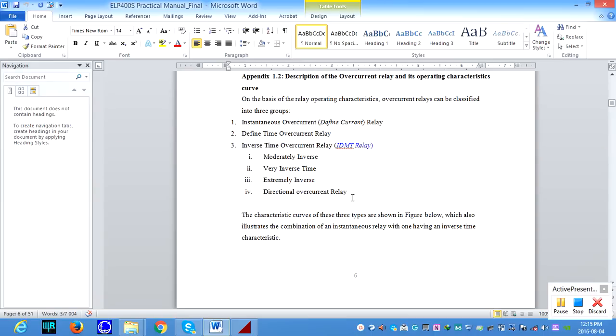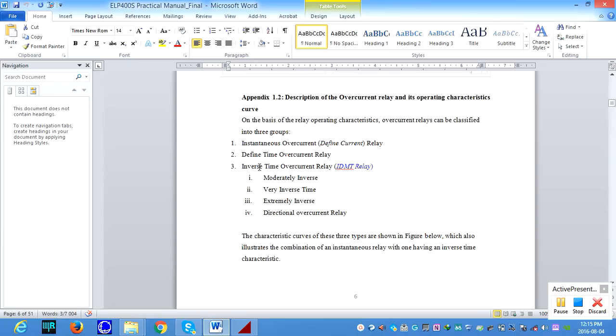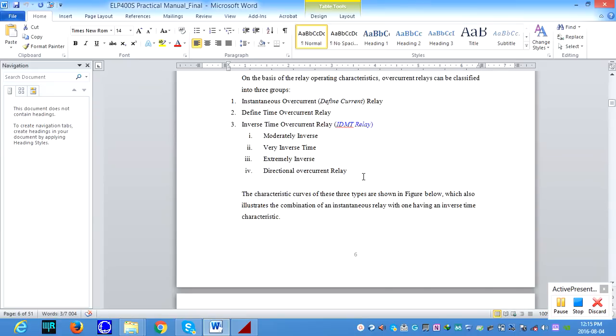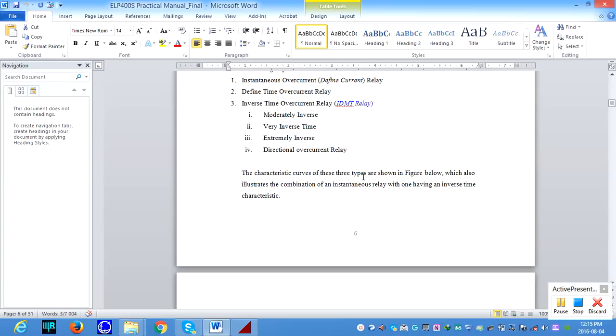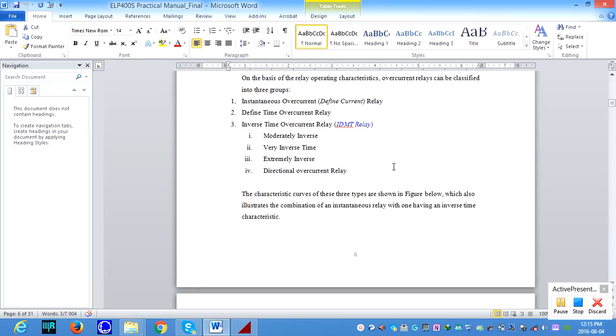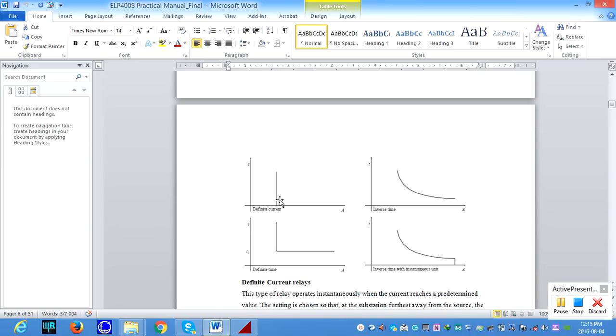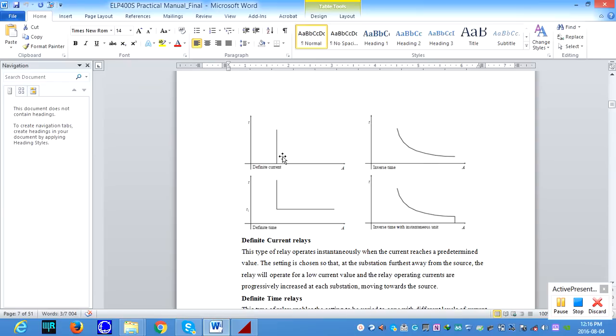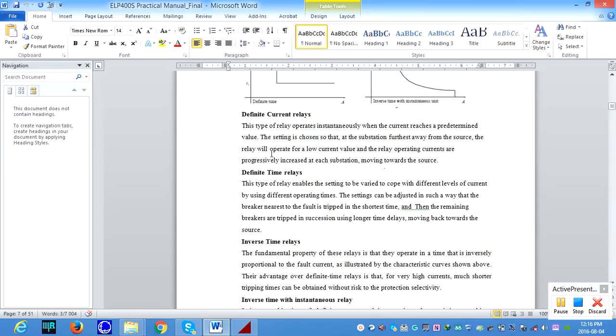The overcurrent relay is defined into three categories. One is the instantaneous or definite relay. The second one is the time overcurrent relay, and the third one is the inverse time overcurrent relay. We basically call it the IDMT relay. This IDMT is further classified into four types: moderate inverse, very inverse, extreme inverse, and directional overcurrent relay. The characteristics you can see for the different types: definite, inverse, and definite time, and the combination of definite time and inverse. IDMT inverse with instantaneous, and the description for each type.